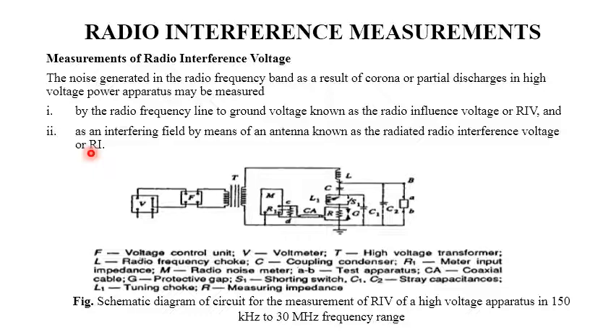This is the schematic representation of the circuit diagram for RIV measurement of high voltage apparatus in the 150 kilohertz to 30 megahertz frequency range. The radio noise meter used in the laboratory consists of a portable radio receiver with a local oscillator, a radio frequency amplifier, a mixer, and intermediate frequency amplifier detectors, with a frequency range of 150 kilohertz to 30 megahertz. In addition, the radio noise meter has multiple input circuits to accommodate a number of pickup devices, attenuators, calibrators, and an output circuit consisting of special detectors and meters.